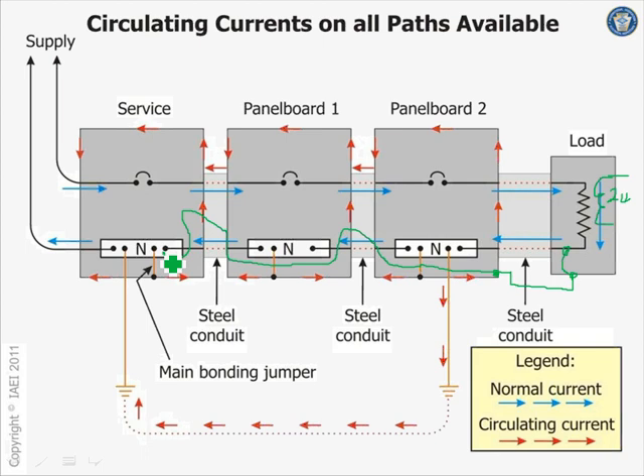I hate to go to the high voltage. In the high voltage business, like 13.8 kV, if you move from here to here, I can't remember, 2,000 or 3,000 feet, which is a really high distance, the voltage between the ground and the neutral starts going up the further away you go. On the low voltage system, it's not an issue. In the high voltage system, that's why utilities, on the power poles, every two to three poles, ground the neutral again. They force the neutral to go back to the ground. Because the further you go, the impedance gets bigger, and you could create a voltage difference between the neutral, which is grounded at one point, and the ground 200 feet away. You could create like a 400 volt difference between them, enough to kill people.